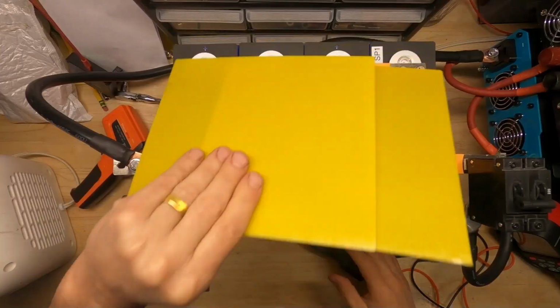I mean, if you want to scrutinize anything, it's definitely the bus bars. We see near 200 degrees, that's crazy. Which I'm kind of surprised, especially with the double studs having those large surface areas to mate with the bus bars. I'm surprised it got that hot. So I just realized something. I was using the aluminum bus bars.